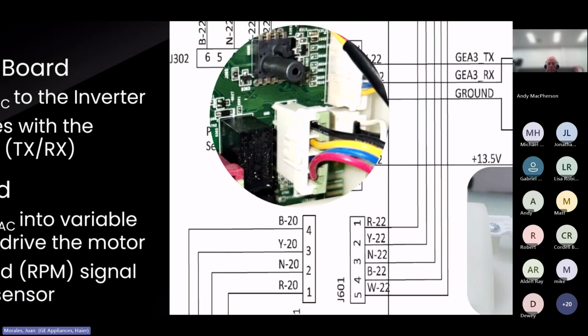That black tube sticking out from the board, that's your pressure sensor, where the hose gets connected. It's very important that you check that hose because sometimes it can get pinched or cut. Something as simple as that will cause the machine to give you all sorts of trouble.